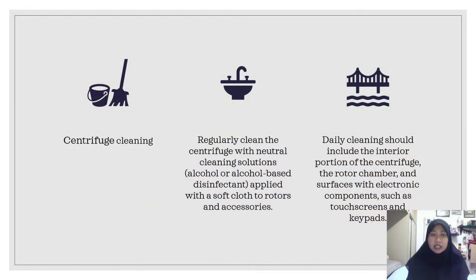Centrifuge cleaning. Regularly clean the centrifuge with neutral cleaning solutions, such as alcohol or an alcohol-based disinfectant, applied with a soft cloth to the rotor and the accessories. The daily cleaning should include the interior portion of the centrifuge, the rotor chamber, and the surfaces with electric components such as the touchscreen and keypad.